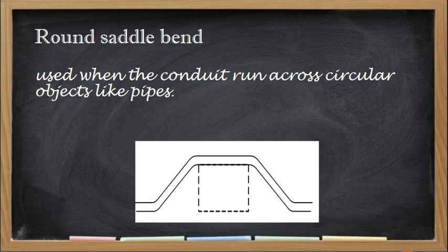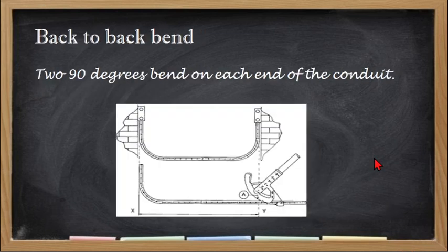The last one is the back-to-back bend. The back-to-back bend has two 90-degree bends on each end of the conduit. It is usually used when we have two boxes and our conduit is running horizontally, but we need to go up vertically on each side. So we need two 90-degree bends, which is called a back-to-back bend.